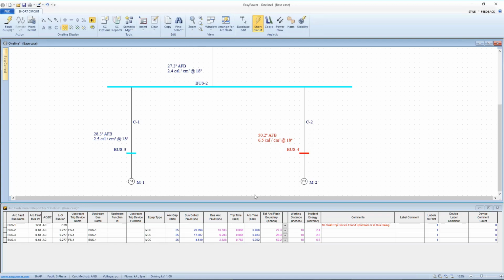But now, we put all those numbers into the IEEE equation, and we show we have an arc flash boundary that's quite a bit higher and an incident energy that's quite a bit higher than the other 2 buses. So what it amounts to, if I'm wearing the same PPE as I had on when I worked on this transformer terminal, the explosion from a fault that I was working on down here would be 10 times longer than the explosion that I'd be exposed to on the transformer. So consequently, that PPE would not be near adequate for my protection. So that's what I refer to as the arc flash paradox.